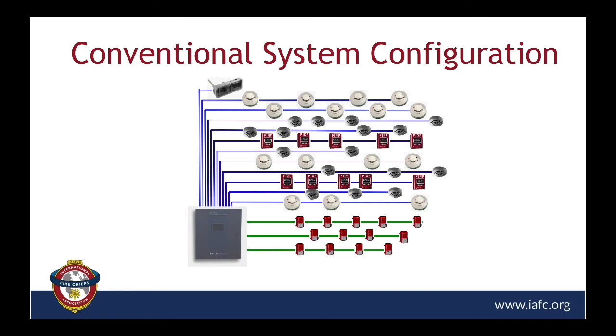Here's a good diagram of a conventional system. You see the panel here near center bottom, and you see a blue line, which in essence is a pair of wires, or a circuit, or a zone for each group and type. These things can be zoned on a by-floor basis. You might walk into the building and it'll say first floor, period. But it might also say first floor smokes, or first floor pull stations, or duct detector in the roof area. So you can see how the different wiring configurations are aligning here. You can mix these up and set them up in different arrangements. But the fact of the matter is, on a pair of wires, you can connect up to sometimes as many as 30 devices. And as your first responder, all you're going to know is that the fire is in that area or zone, and you're going to have to search to find exactly where that initiating device is coming from. We'll come to the solution to that in a moment.